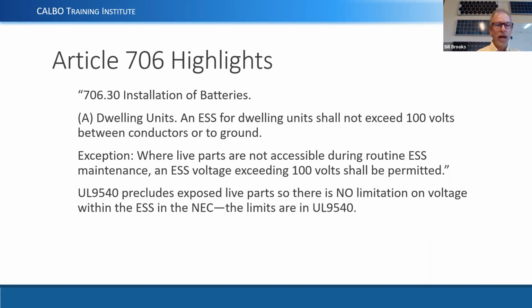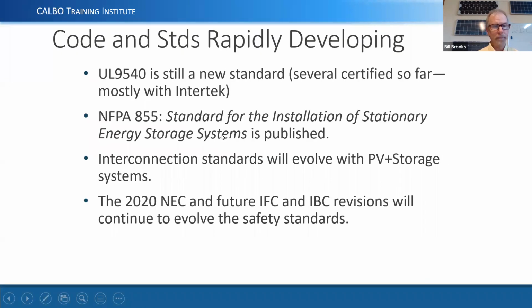no problem. So UL 9540 precludes the need for these voltage limitations. There are essentially no voltage limitations on your UL 9540 equipment, and this part of the code really doesn't apply to anything.